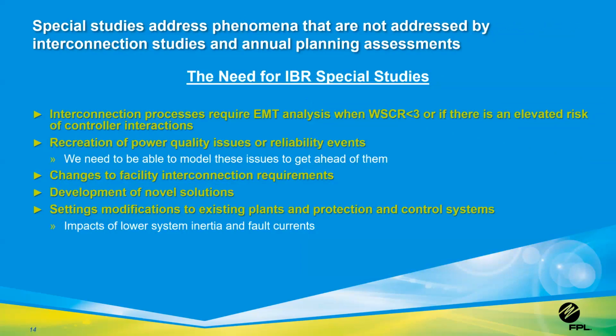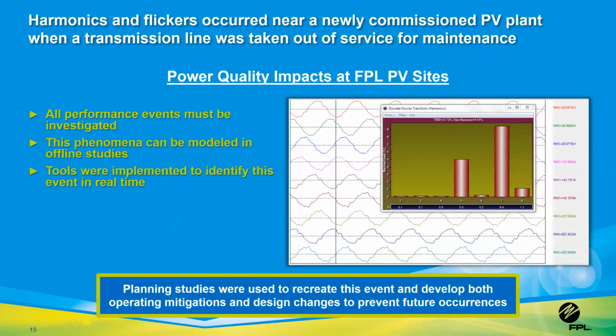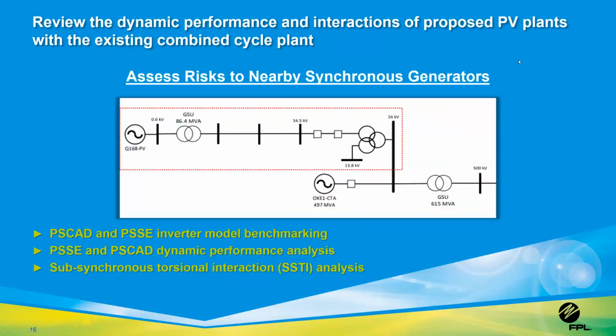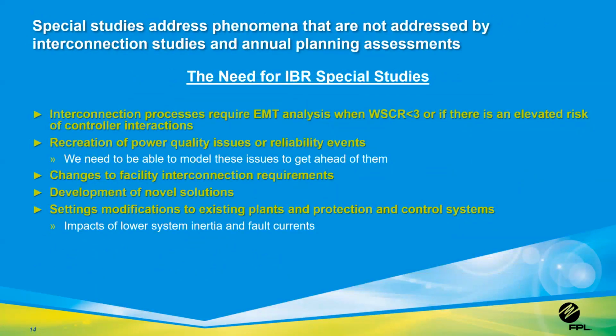So why do we need special studies for inverter-based resources? Why can't we capture all of these reliability issues through interconnection studies and annual planning assessments? One reason is that detailed EMT analysis is very time-consuming and is currently infeasible and, quite frankly, unnecessary to do for every proposed generator. At Florida Power and Light, we perform these studies when the weighted short-circuit ratio is less than 3, or if we have some other reason to be concerned about controller interactions.